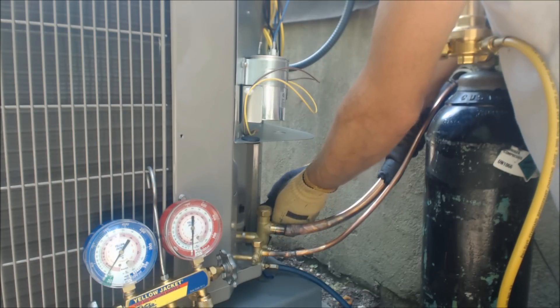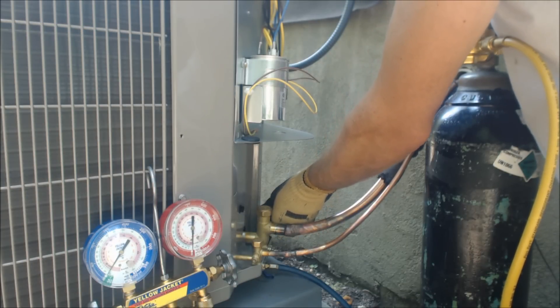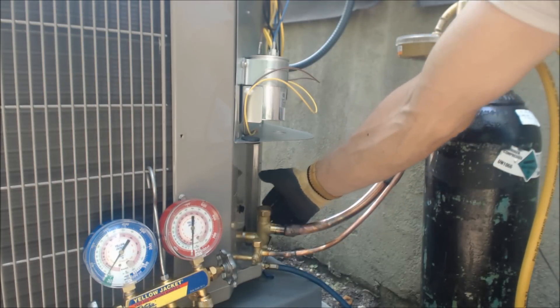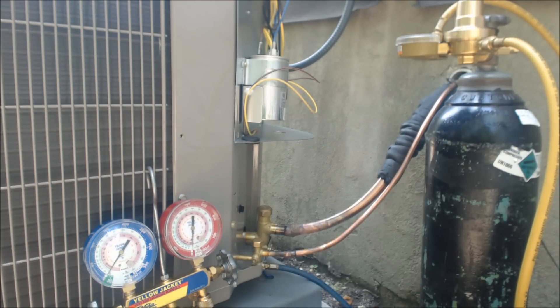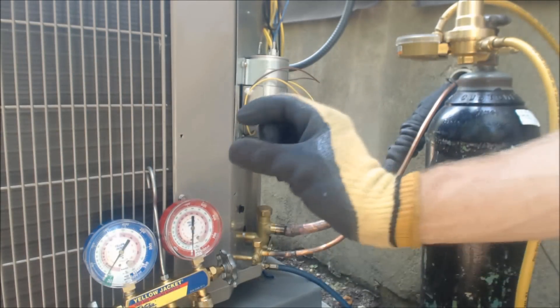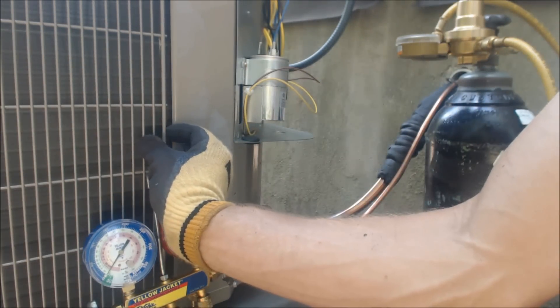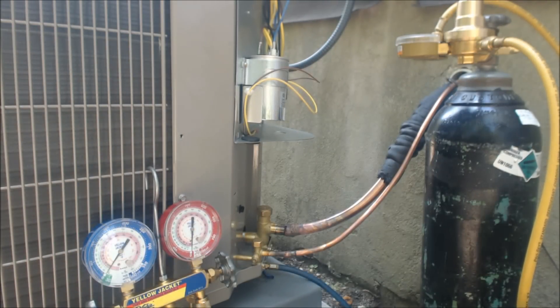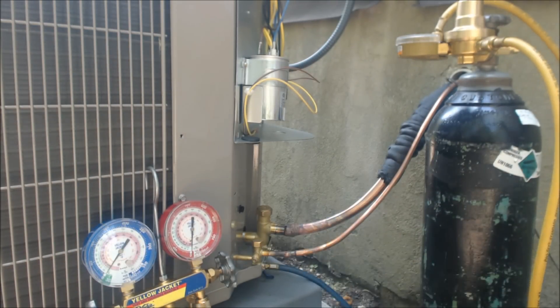If this was an existing system where you're reusing the line set or the evaporator coil, you'd want to do a oil blowout first — flowing nitrogen through one side and blowing it out the other line. You want to do that before even running a vacuum pump, because the micron gauge won't work properly otherwise. You can end up with trapped air from globs of oil traveling in the line. But this is all new — new condenser, new line set, new evaporator coil — so we don't have to do an oil blowout.